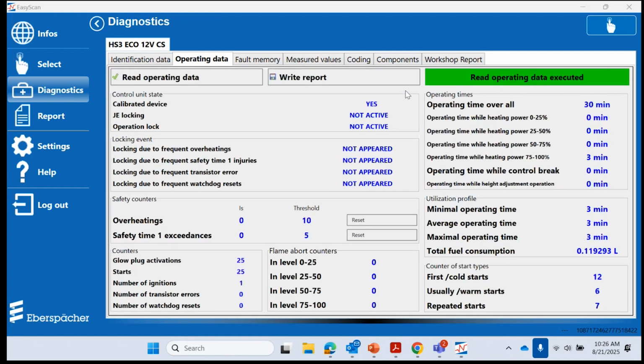Operating data shows us overall the operation of the heater: operating times, utilization profile, number of starts, loss of flame, counter values, etc. Right here in the middle is the safety time counter values. You can see the maximum threshold both for overheating and safety time. And this is the current value. So for example, if you have 10 overheatings, then that matches the threshold 10, and then your ECU will be locked. In that case, all you have to do is press the reset button. If you press the reset button, this counter goes back to 0. And the same applies to safety time.